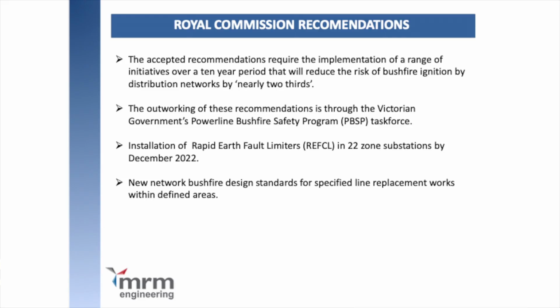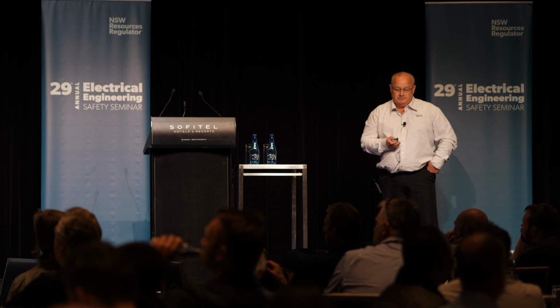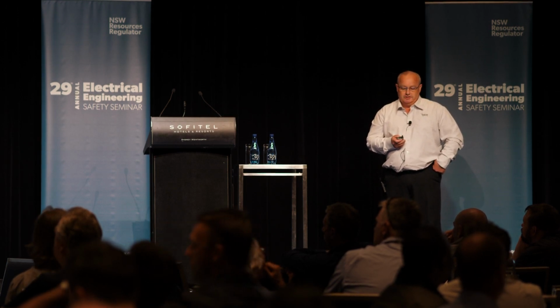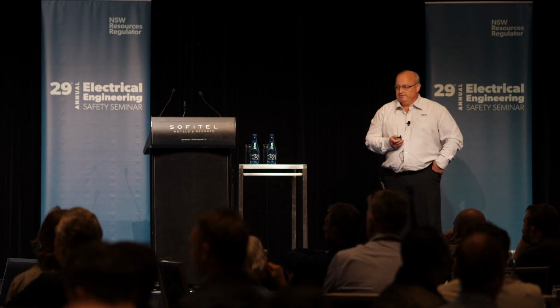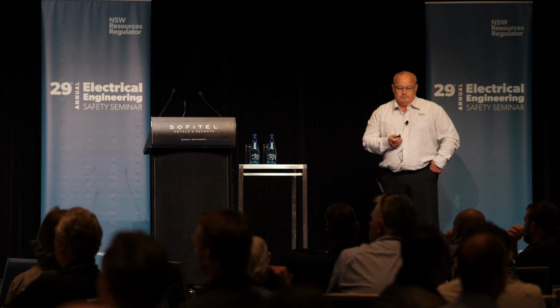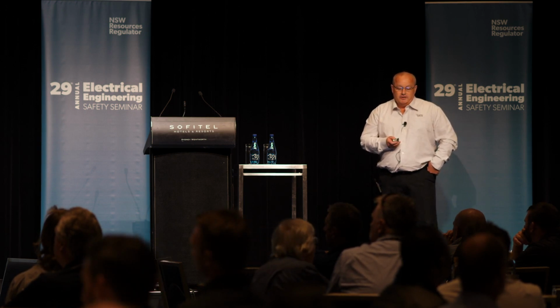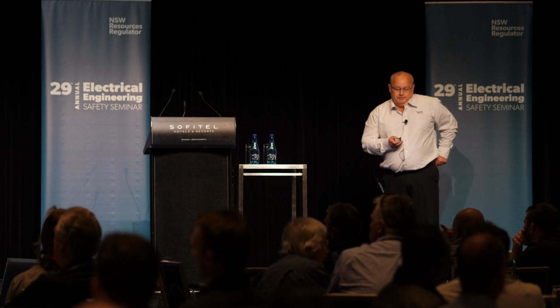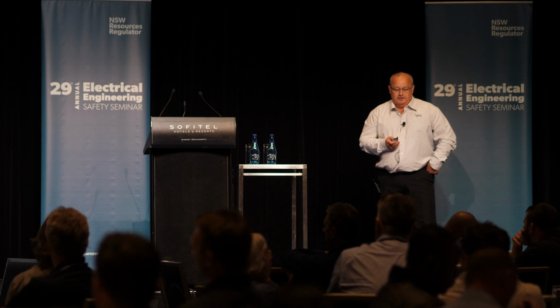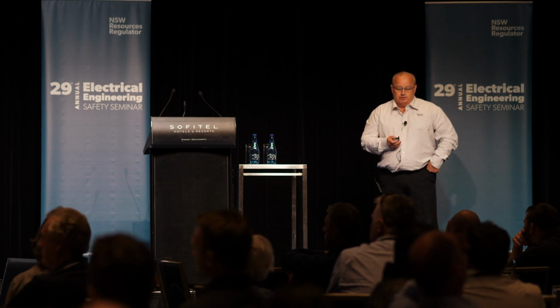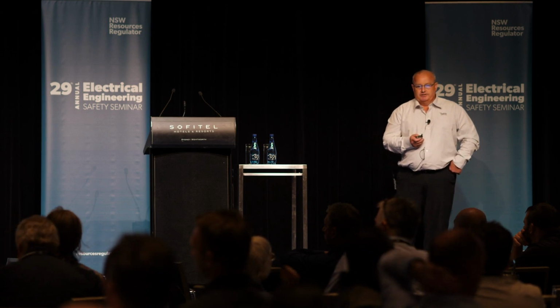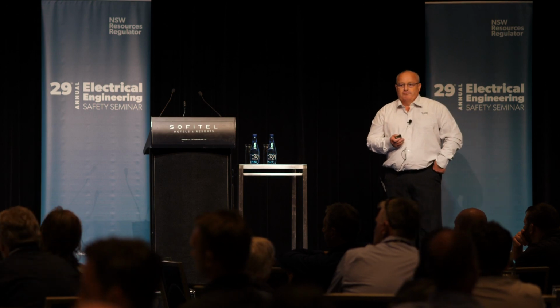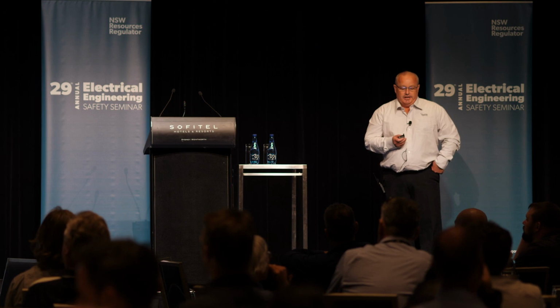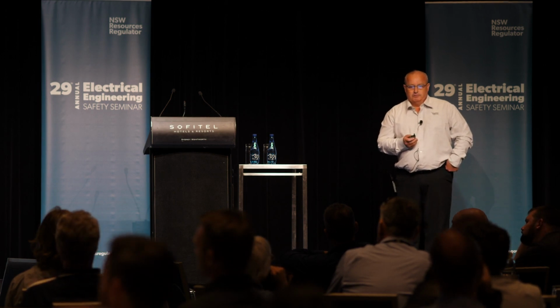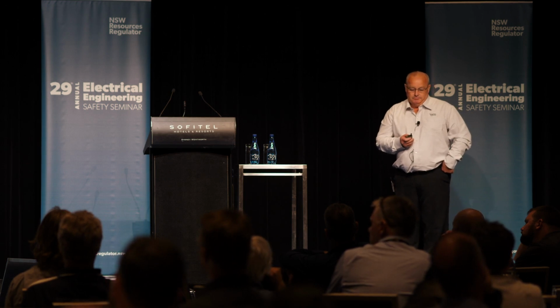So from the Royal Commission, they ended up with some recommendations. The accepted recommendations require the implementation of a range of initiatives over a 10-year period to reduce the bushfire ignition risk by two thirds. That's a pretty substantial requirement to actually get bushfires down due to the network or the distribution networks. The outworking of these recommendations through the Victorian Bushfire Safety task force ended up in the installation requirement of 22 rapid earth fault limiters in substations by December 2022. As far as I'm aware, the first one's going to go in June next year, and I've been doing some investigation work around the compliance of the load side of the implementation of the rapid earth fault current limiters.